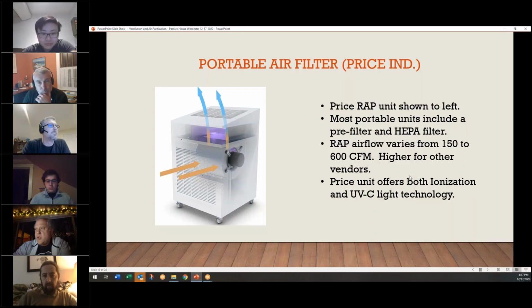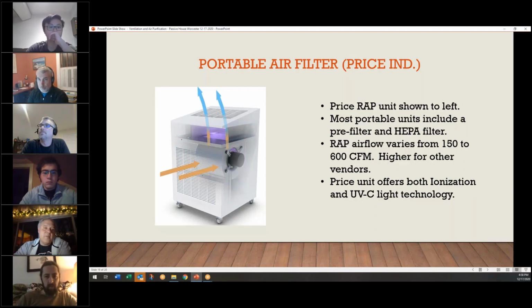The Harvard T.H. Chan School is recommending that if you get one of these, just focus on the HEPA filter, right? Their comment is, look, we don't know all the interactions that may occur with the UV lights and the catalysts and the ionizers. Maybe there's something in that room that nobody knew about, like an open bottle of Ajax or something, and it reacts with something and creates something that you didn't expect. So their tack is to just put the HEPA filters in and focus on that. But to the other point, if you put the ionizers in, you could do one air handler and an entire floor of the building and try to provide better quality air for that floor.